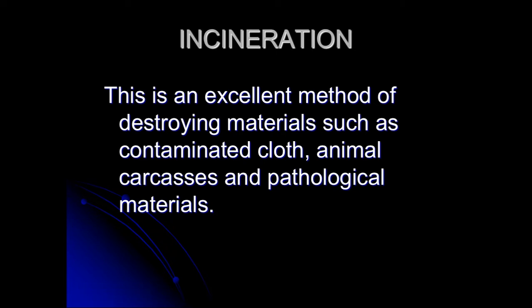Nowadays modern incinerators are available in hospitals. They are double walled, chambered. They operate at very high temperature, that is 800 degrees centigrade for the first chamber, and the second chamber has a temperature of 1000 to 1200 degrees centigrade. So all the infected material subjected to incineration will be converted into a small quantity of ash, even though it is present in large amounts. That process is commonly performed in hospitals, that is the process of incineration.